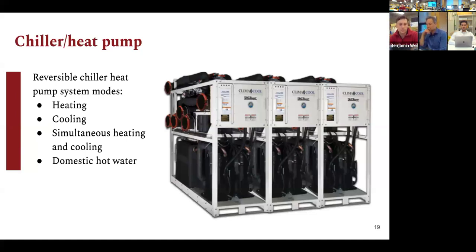So a reversible chiller heat pump system, during the warmer months, will function as a chiller, removing heat from the building's air. And in the colder months, it acts as a heat pump, extracting heat from the ground and transferring it indoors to provide heating. A reversible chiller heat pump system can heat and cool at the same time. And by that, I mean if one part of the building requires cooling and one requires heating, it can do that simultaneously.